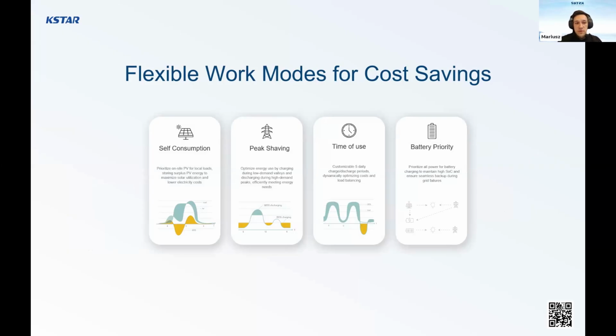Regarding the flexible work modes, we are providing mainly self-consumption. This is for the main use: if the PV is enough to cover the loads, we cover the loads. If we have too much PV, we can charge the battery, but we can also combine these working modes with battery priority by selecting different percentages, different SOC levels, for on-grid time and off-grid time. That means we can make it a little flexible, and also peak shaving. It's something that will sometimes be used by customers, but it's not so important in residential. Time of use is mostly used by third-party controllers, but we can also set up some times of charge and discharge in self-consumption mode.